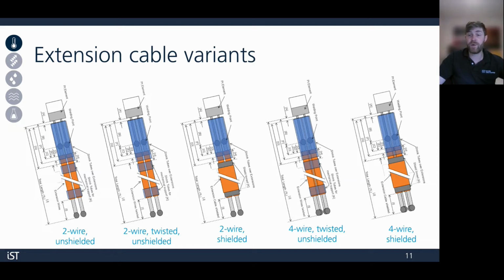So if your electronics support it, a 4-wire measurement will always give you the most accurate result, since you can subtract the wire resistance from your overall measurement and you're left with the resistance of the RTD chip itself.